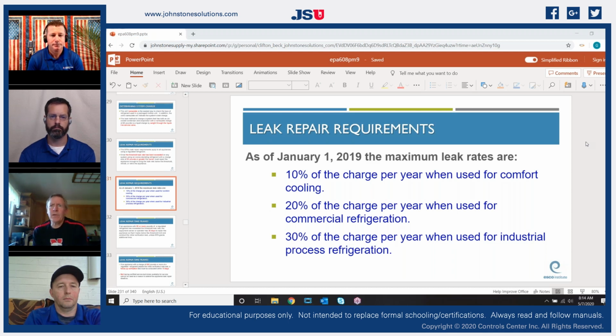And a lot of times what will happen is if you charge a residential air conditioner in the spring and it runs all summer, but the next spring it's quite low, a lot of times it leaks at the evaporator because that's a coil that's been heated over the winter and expanded the refrigerant and it leaked at a faster rate. So you just try to determine through the leak rate where the possible leak would be, because a lot of guys have a lot of trouble finding leaks. I didn't seem to have that much trouble, and I didn't use electronic. I was never any good with them.